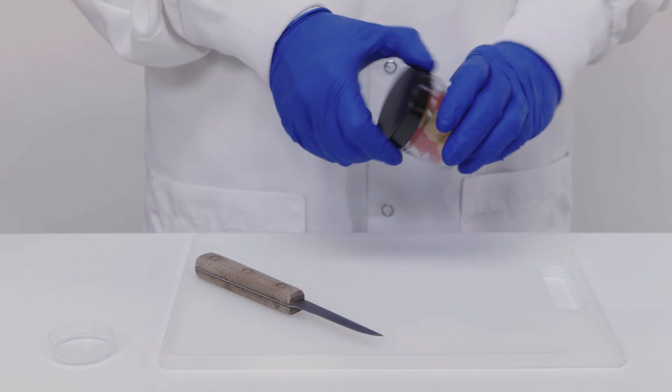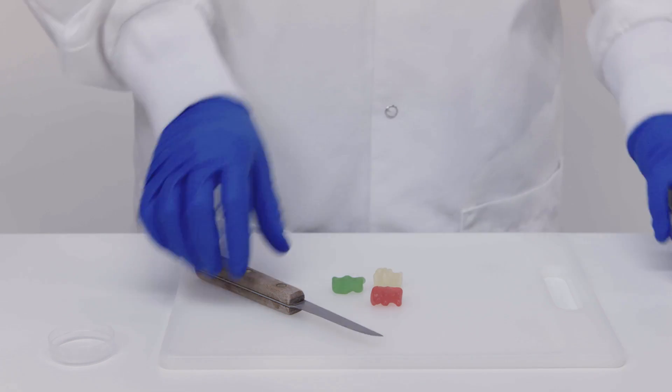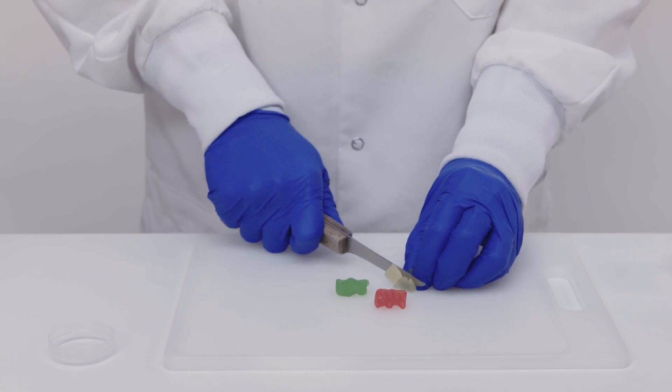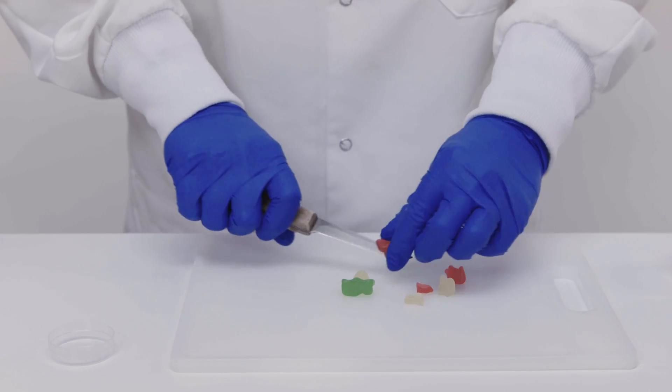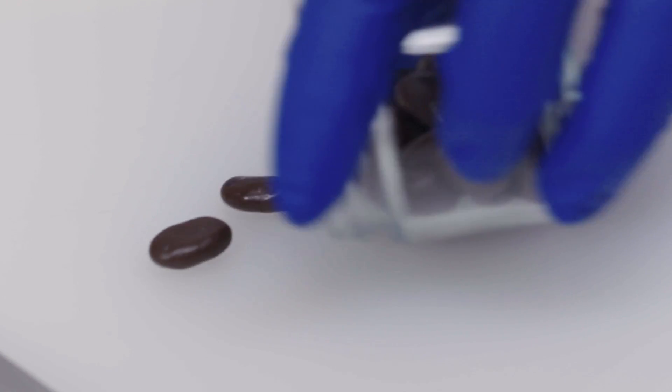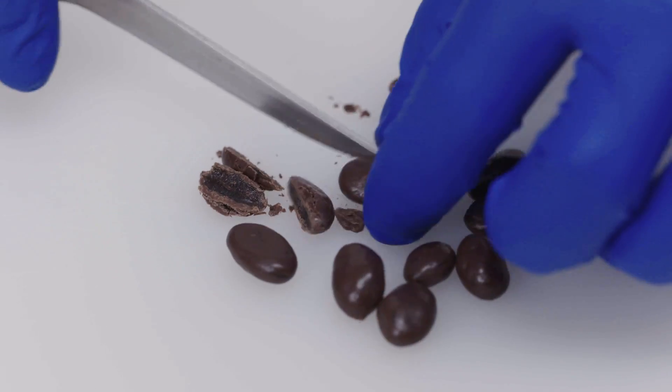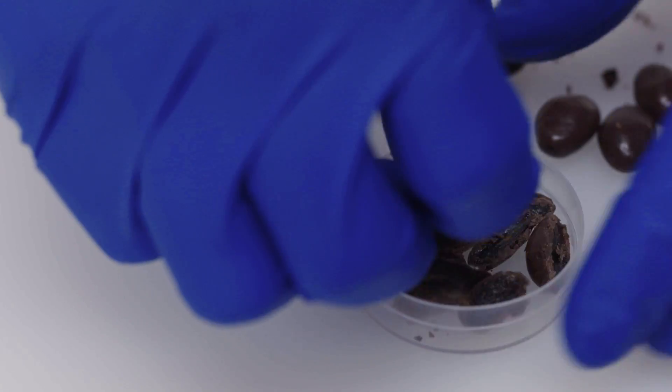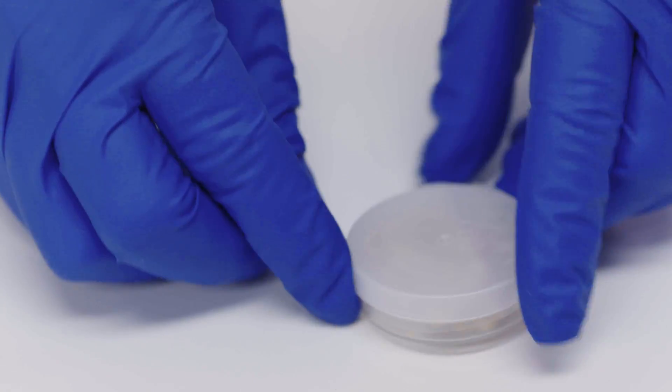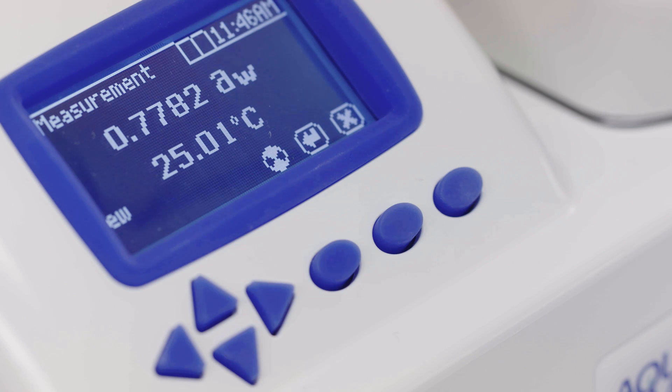In sample preparation, less is more. We've seen customers use all kinds of sample prep methods over the years, including grinders, food processors, and blenders. There are two problems here. First, the friction of the grinding process heats the sample, driving off moisture and changing its water activity. Second, the increased surface area means that the product loses or gains moisture more quickly, making it more susceptible to the effects of room humidity. Establish a standard operating procedure to specify how samples are prepared and be consistent. Your procedure should include how the sample is handled while waiting to be read and the temperature the sample and instrument should be at during the reading. When you set up this protocol, consider running your own tests to find which preparation method produces the most stable result.